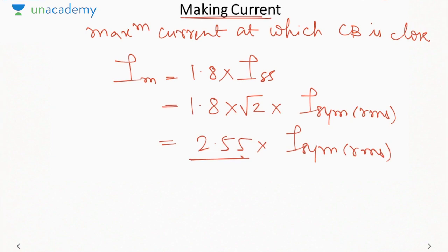So in any question, if the making current is being asked, you will multiply a factor of 2.55 with the symmetrical breaking current. So these two ratings are very important when it comes to the circuit breaker: one is your breaking current, the other is your making current. Now, let us discuss the types of circuit breaker based on the construction or the material being used between the plates, and we will discuss the advantages and disadvantages of each type.